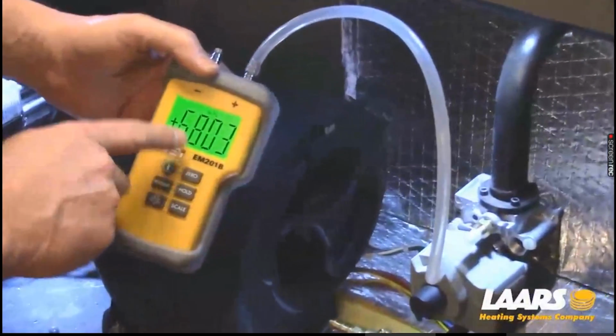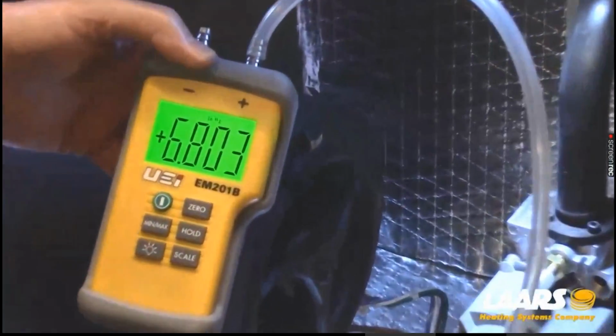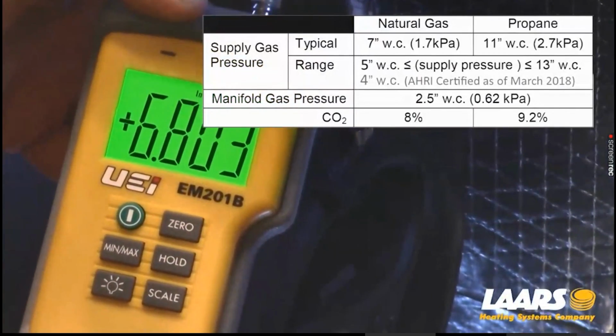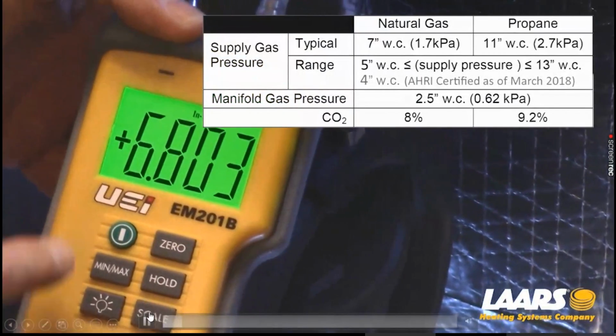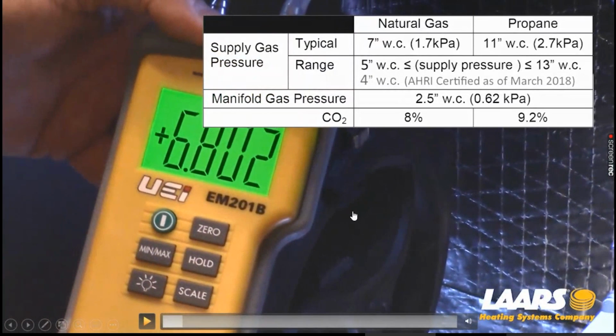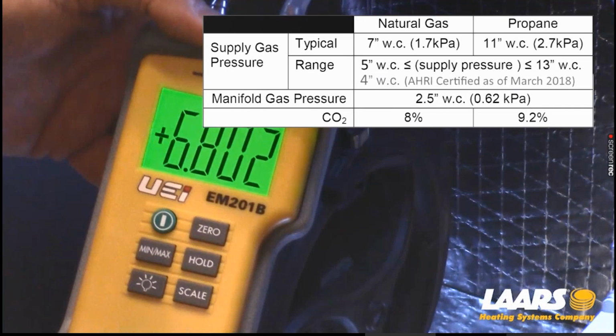So now you can see we have 6.8 inches of water column coming into this boiler. This boiler requires a minimum of 5, maximum of 13 inches of water column. Now, I just mentioned a minimum of 5, maximum of 13. So the earlier products, we were certified for 5-inch minimum, maximum 13. We were recertified by AHRI in 2018 for 4 inches. That was March of 2018. So read your rating plate, which is on the right-hand side of the boiler, and it'll give you that range, minimum and maximum gas pressures.